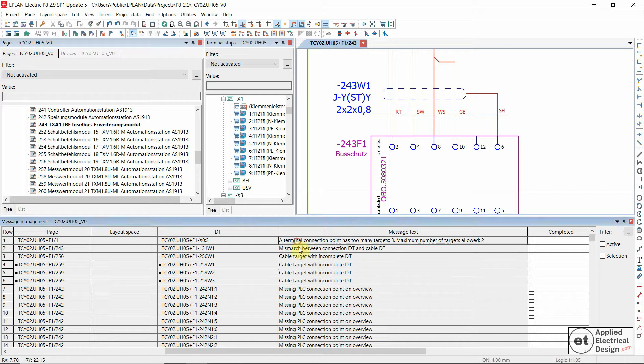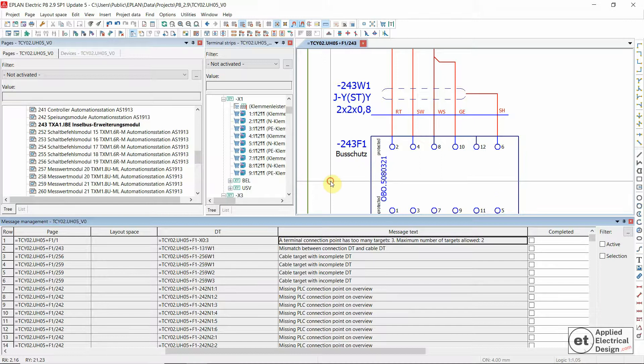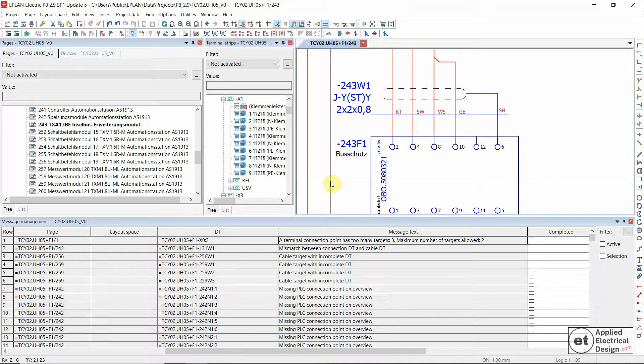Let's now see this message. A terminal connection point has too many targets - three. Maximum number of targets allowed would be two. This means that we tried to connect three wires into one terminal. Normally the maximum would be two wires.